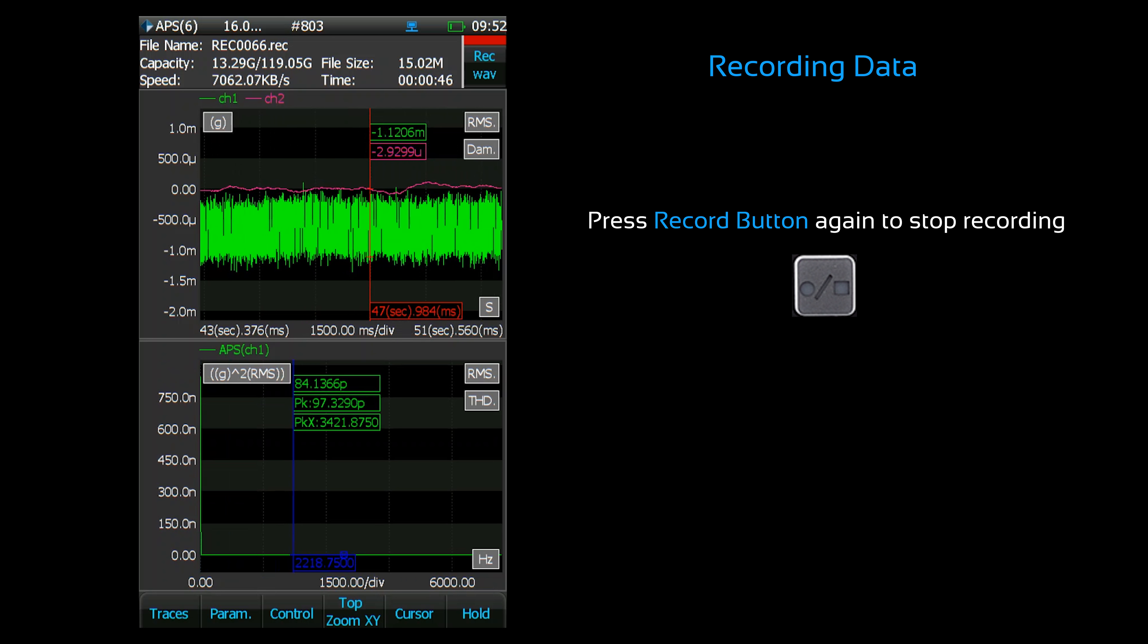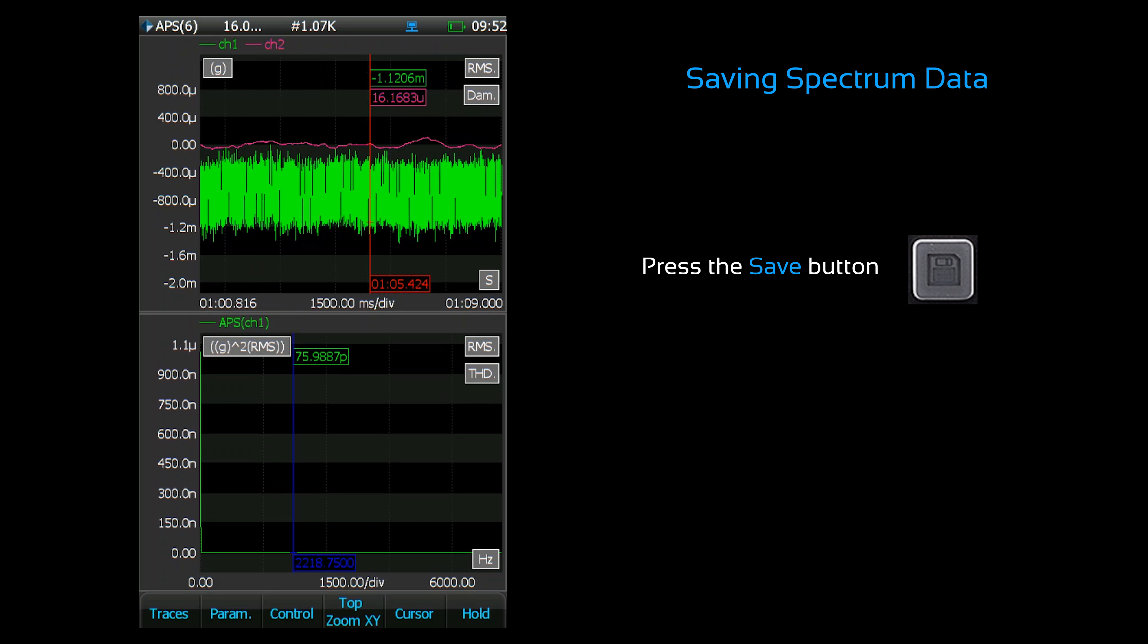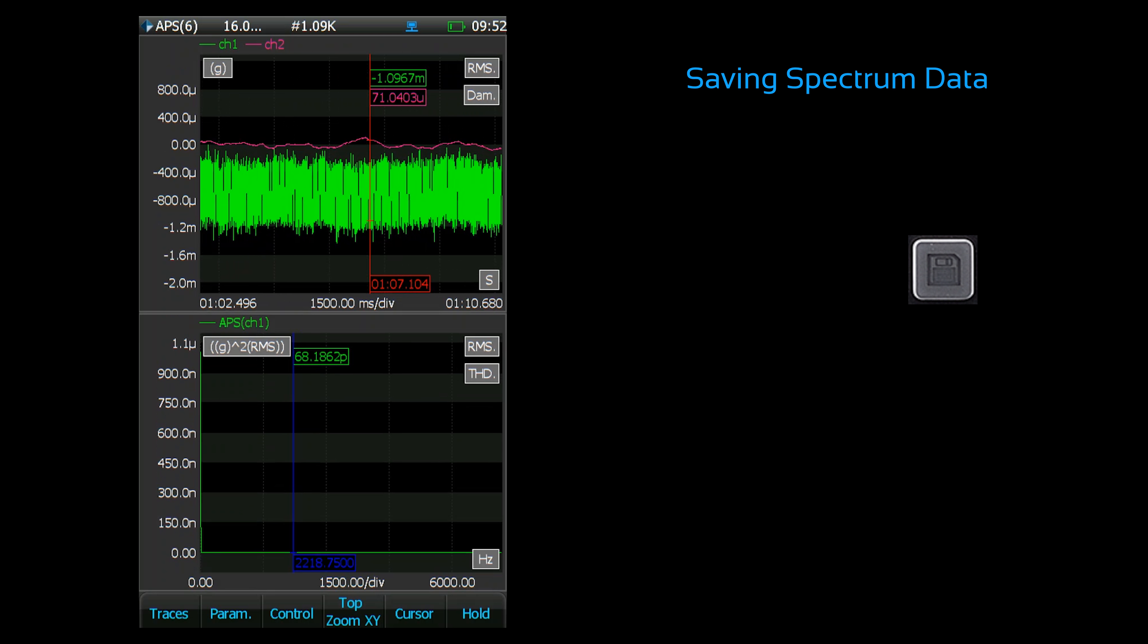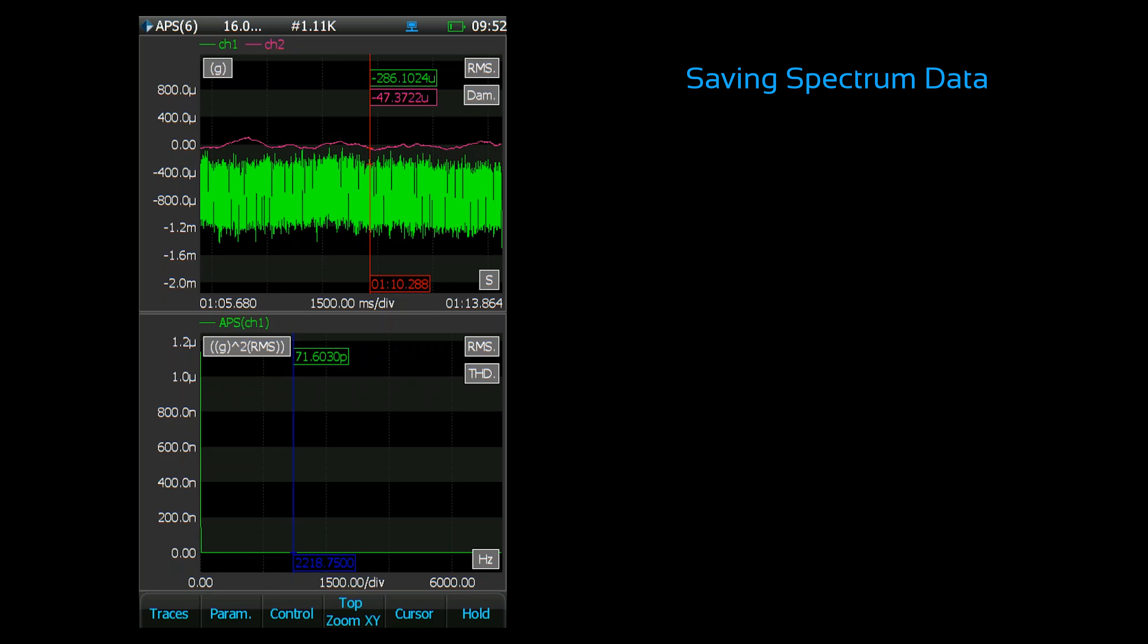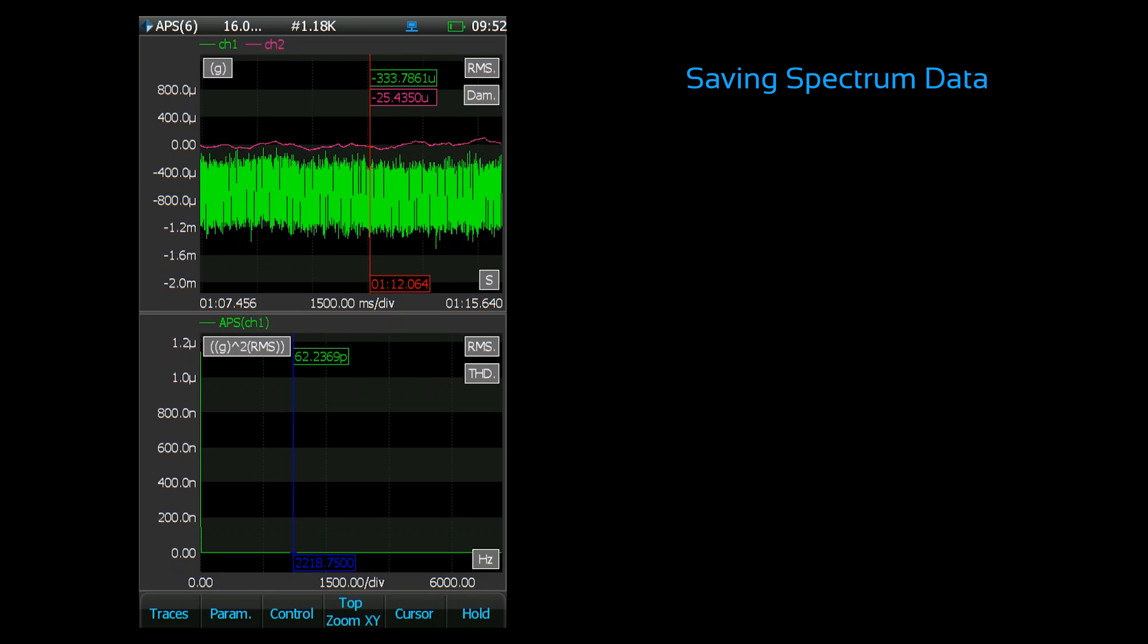To stop the recording, press the record button again. Now let's save a signal. Press the save button to initiate saving. This time the status banner only displayed for a moment. This is because it was configured to save only a single frame. This can be changed in the spectral save setup.